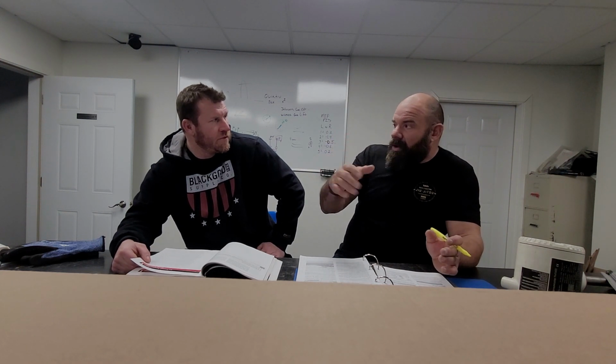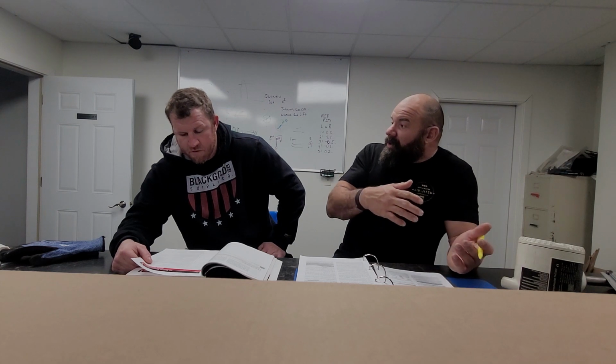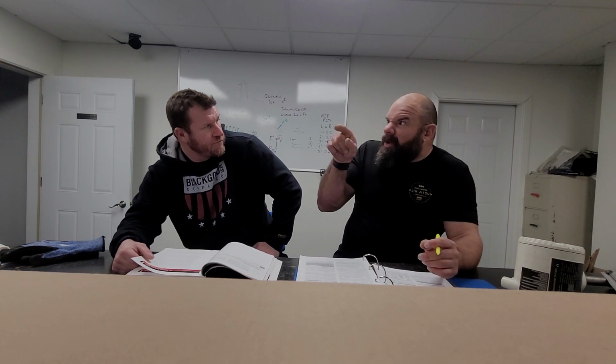Now, if you're by the ocean, you want some extra protection, sure. Maybe you're in a saltwater facility, you don't want oxidation for that. But the code doesn't say, as a rule, you have to use it all the time. Probably long-term good practice, but it's not required. I know inspectors will say, that's an aluminum conductor, it doesn't have it on there, you should fail this. No, it's not required, especially for the aluminum that we use now.